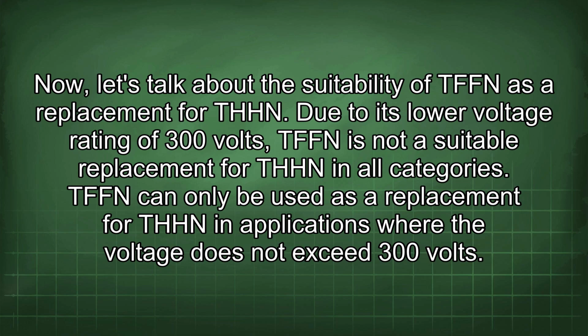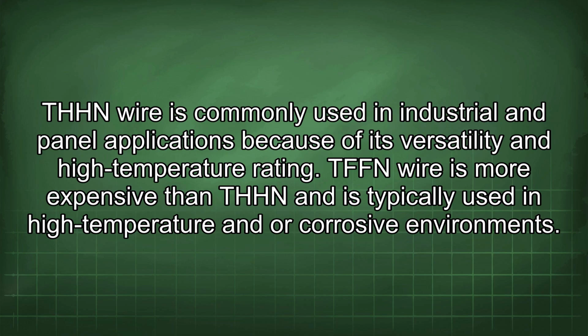Now, let's talk about the suitability of TFFN as a replacement for THHN. Due to its low voltage rating of 300 volts, TFFN is not a suitable replacement for THHN in all categories. TFFN can only be used as a replacement for THHN in applications where the voltage does not exceed 300 volts. THHN wire is commonly used in industrial and panel applications because of its versatility and high temperature rating. TFFN wire is more expensive than THHN and is typically used in high temperature and or corrosive environments.